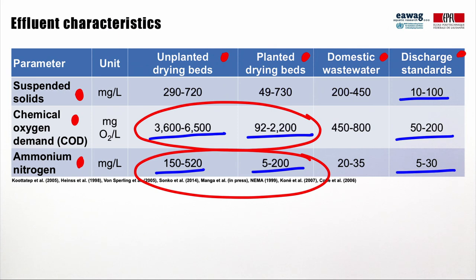Thirdly, even after solid-liquid separation, these effluents can have much higher concentrations than the influent of a domestic wastewater treatment plant. For example, whereas the suspended solids concentrations in the leachate from drying beds are somehow similar to domestic wastewater, COD and ammonium concentrations can be one order of magnitude higher.